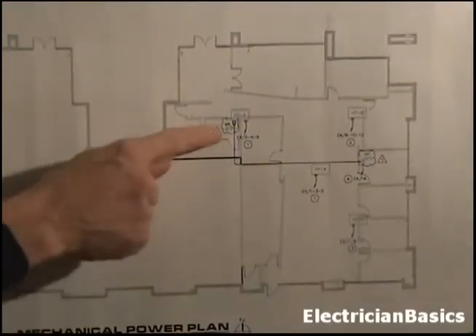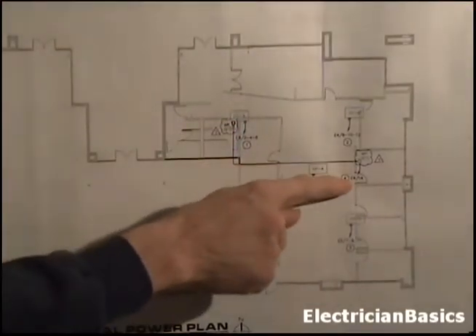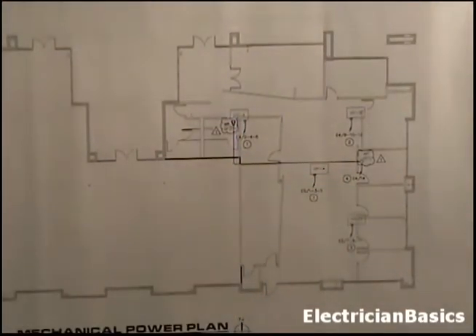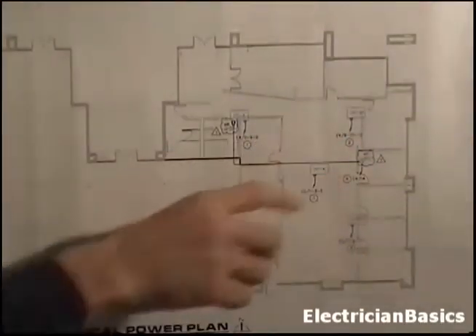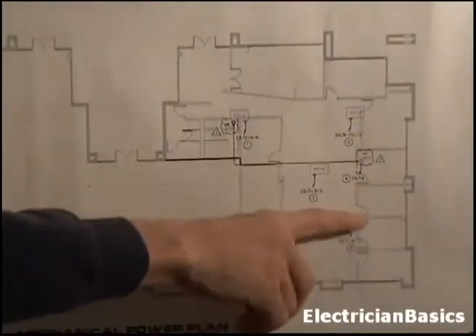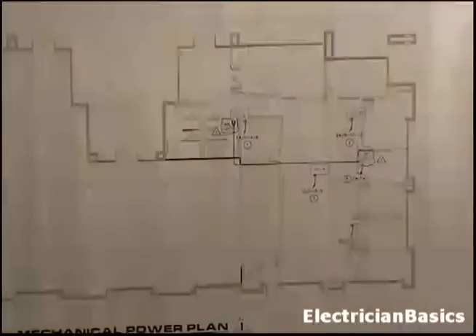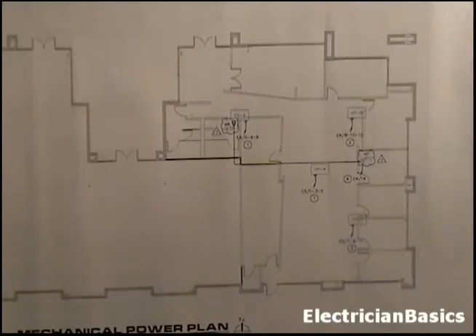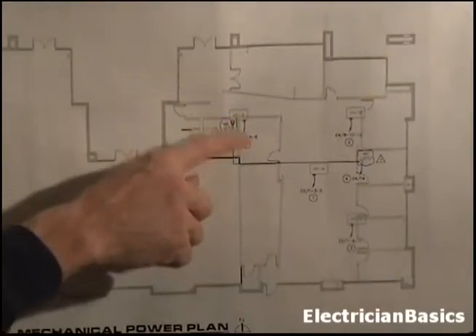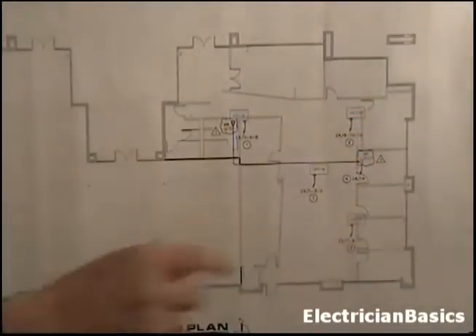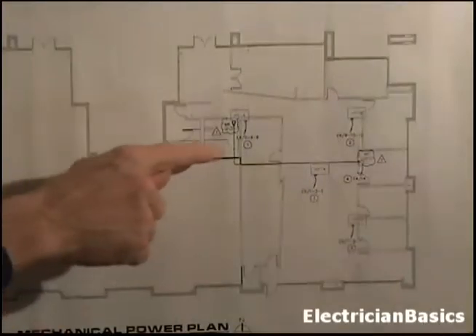Another thing we see here, we got this line E4 circuit 14, and we have a note 4, and it says 3/4 inch conduit, 2 number 12 wires, number 12 ground, be used for each 20 amp circuit. These are the convenience receptacles for your roof. Within a certain distance of each of these heat pumps or any piece of equipment on a roof, you have to have a receptacle so that if you have to do maintenance work on that piece of equipment, you have electricity there. So here you have one over here, and this one will be shared by these 3 because it's close enough.